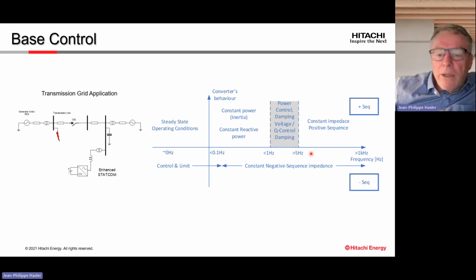For the negative sequence it is much simpler. We always keep the same impedance, whatever the frequency. That means we don't have any special control. The negative sequence current will be defined only by this virtual impedance, nothing else.